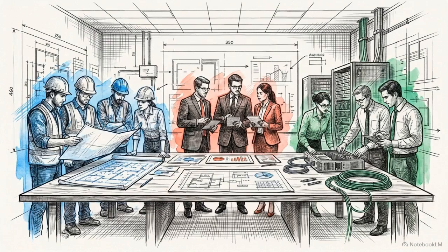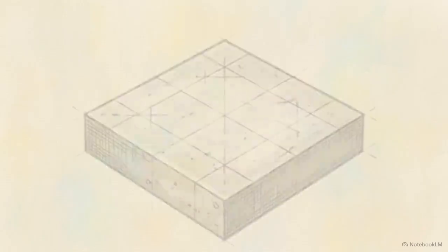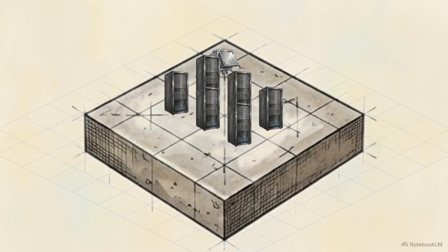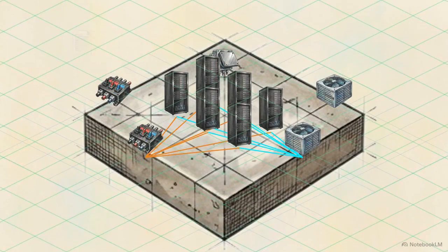Hitting that mathematical margin of error is impossible if you rely on a single engineering discipline. To achieve true enterprise-grade resilience, engineers have to synthesize three highly distinct, heavily regulated industry frameworks into a single facility. First is TIA 942, governing telecommunications topology and physical spatial geometry. Second, Uptime Institute tiers determine mathematical formulas for mechanical redundancy to tolerate faults. Finally, ISO 27001 governs information security, wrapping the hardware in strict documented human protocols.